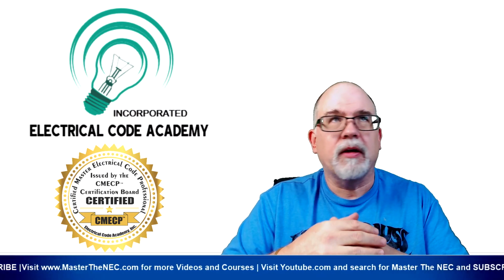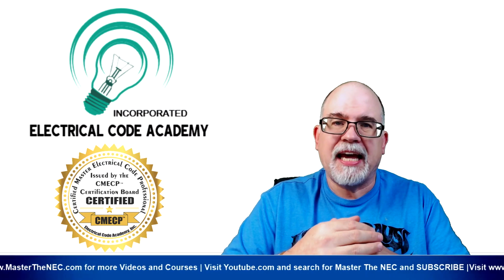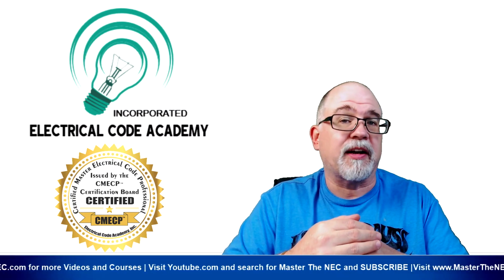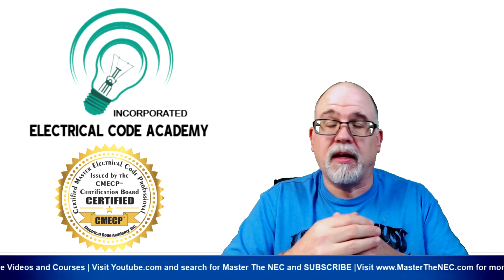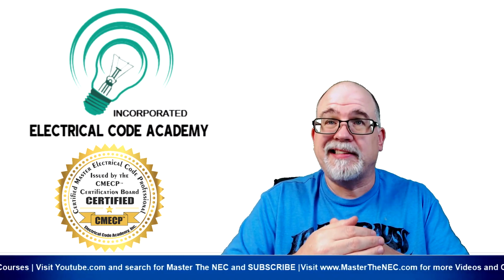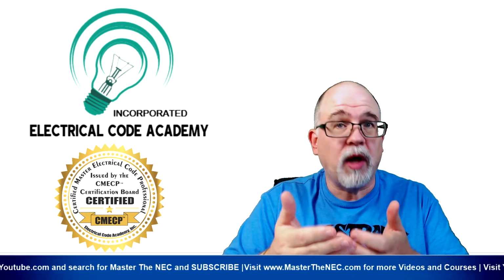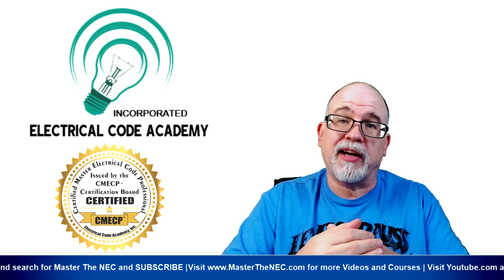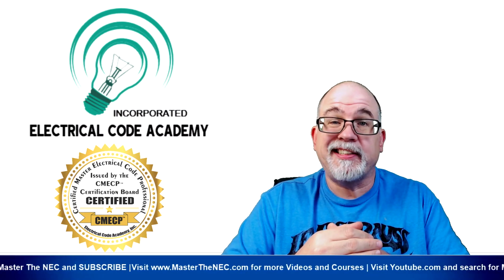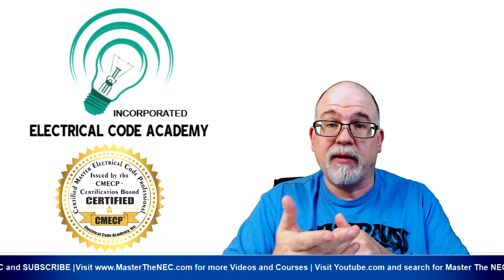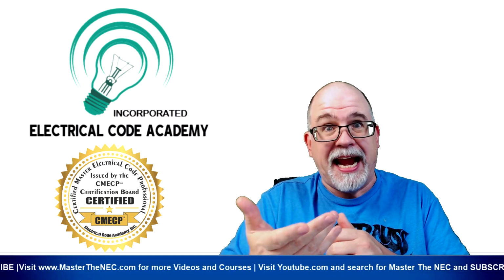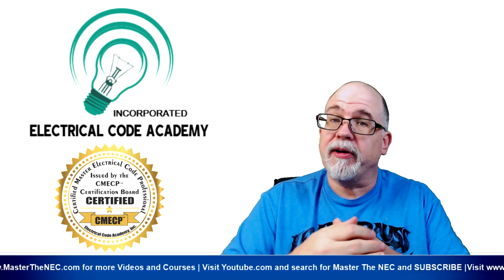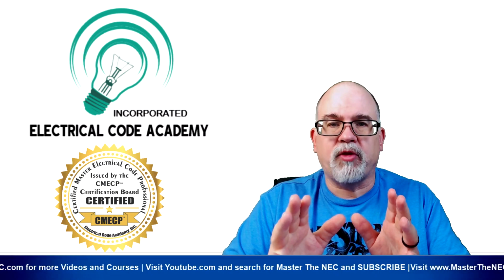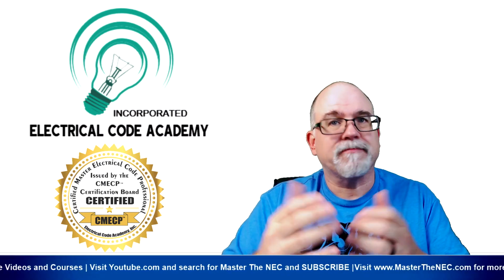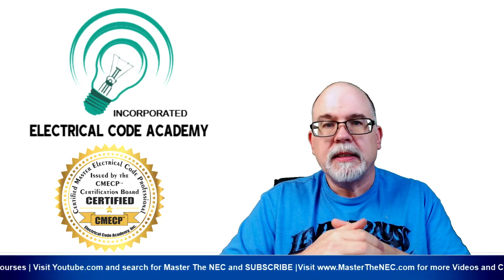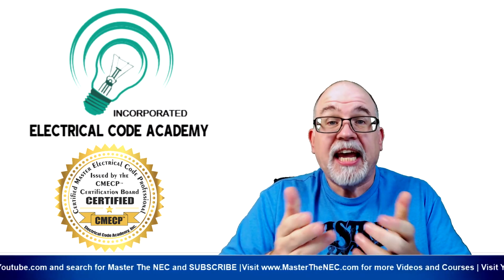Again, we looked at C1, which is really so obscure. On most any other occasion, you're going to have primary and secondary protection of those conductors on the primary and secondary side of a transformer. But remember, if you run into a single phase transformer with a 2-wire secondary and you have 1 voltage value, then the primary could protect those secondary conductors. If you're dealing with a delta to delta and it's a 3-wire secondary with a single voltage value, like a 480 or whatnot, then the primary might protect the secondary conductors. Any other transformer situation, primary and secondary protection, you've got to have it. Okay. So hopefully that was educational for you.